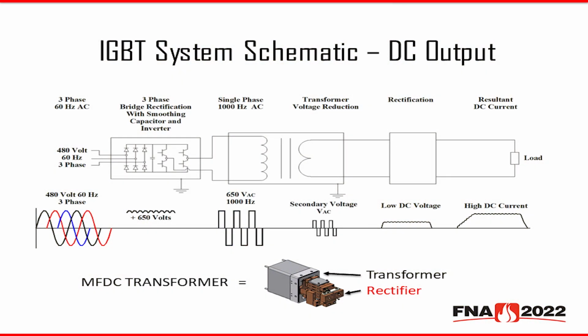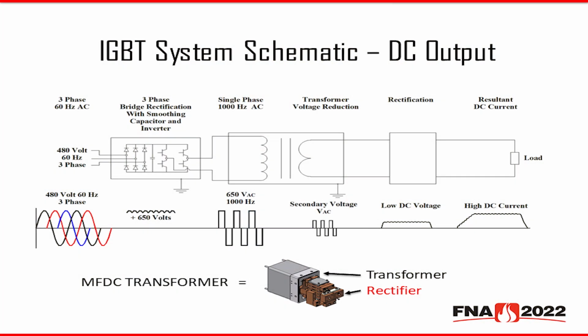waveform at 1,000 hertz. You may ask, well, why did we use 1,000 hertz versus 60 hertz? A good analogy here is the transformers they use in planes. They don't use 60 hertz transformers, they use 400 hertz transformers in planes because that higher frequency allows you to shrink electrical circuits. And this also allows us to shrink our transformer considerably, and then allows us to take that transformer and apply it directly to the power feed-throughs on the furnace. We actually have a power supply at our booth as well, so you can come visit us there to see how much smaller it is. It's a 200 kVA transformer that's about the size of a bread box.